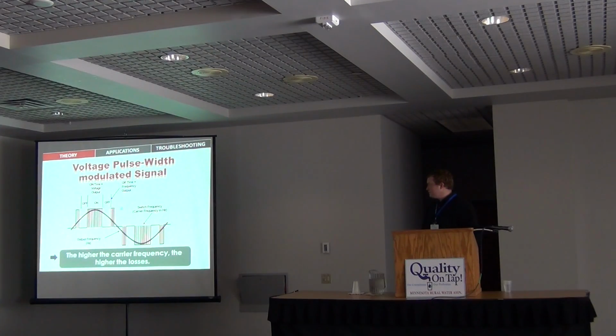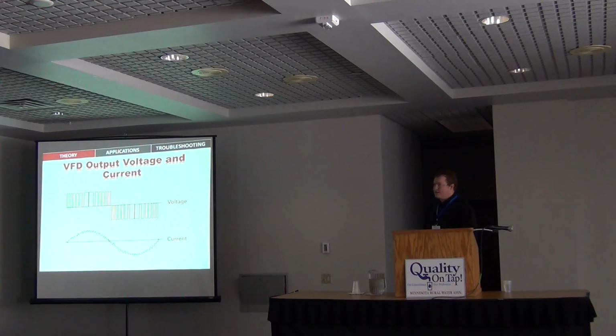So from this, what does it look like at the motor? Because this is showing the modulation, but what are we sending to the motor from our VFD? We're sending something that looks like this. The voltage is all constant, and the width of the pulses are different. And what that's doing is mimicking an AC sine wave using a DC voltage. But because of the properties of the motor, what the motor actually sees for current is this nice shaped sine wave, which is why they work.